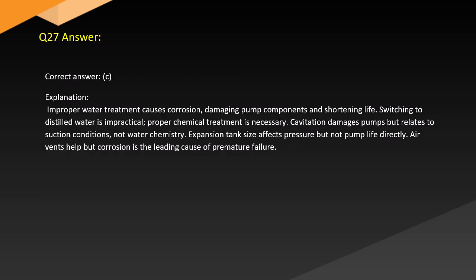Answer. Correct answer, C. Explanation. Improper water treatment causes corrosion, damaging pump components and shortening life. Switching to distilled water is impractical. A proper chemical treatment is necessary. Cavitation damages pumps but relates to suction conditions, not water chemistry. Expansion tank size affects pressure but not pump life directly. Air vents help, but corrosion is the leading cause of premature failure.